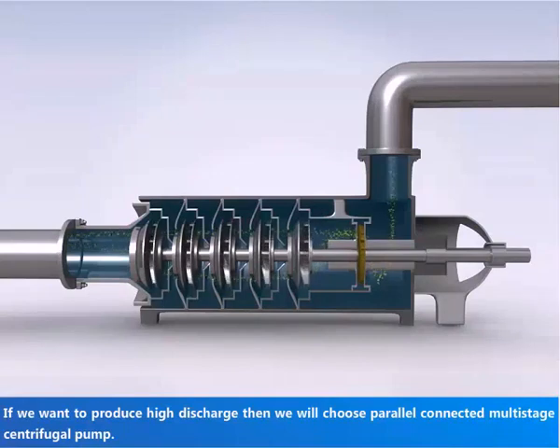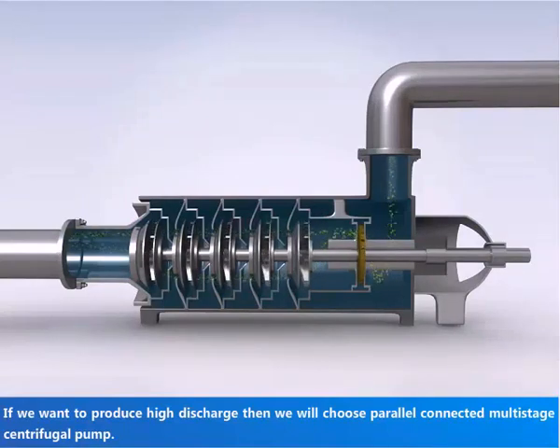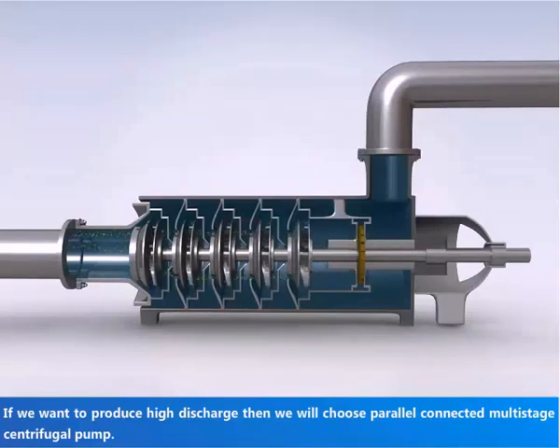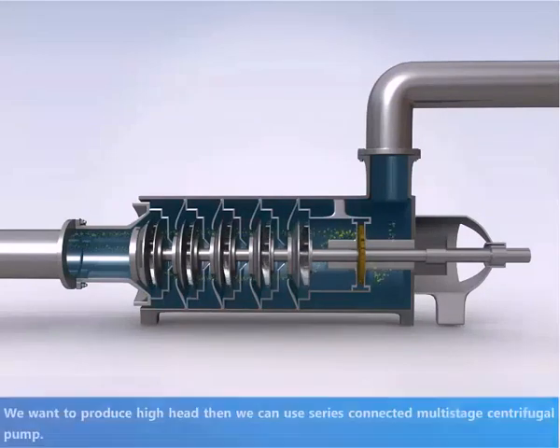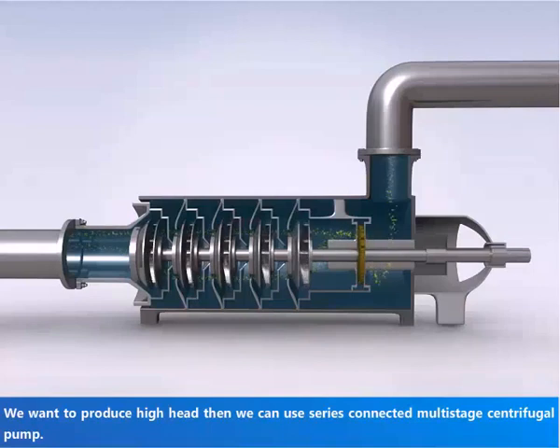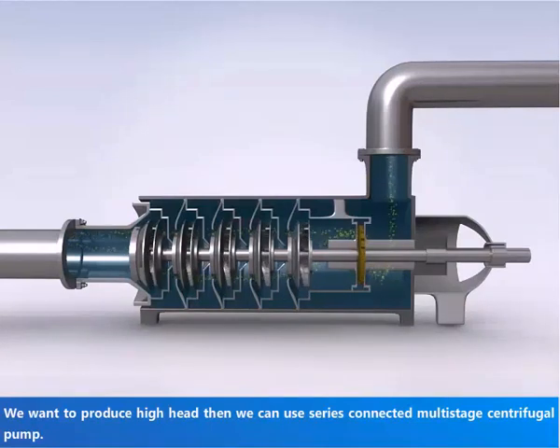If we want to produce high discharge, then we will choose a parallel connected Multi-Stage Centrifugal Pump. If we want to produce high head, then we can use a series connected Multi-Stage Centrifugal Pump.